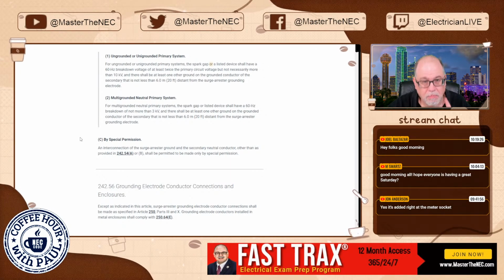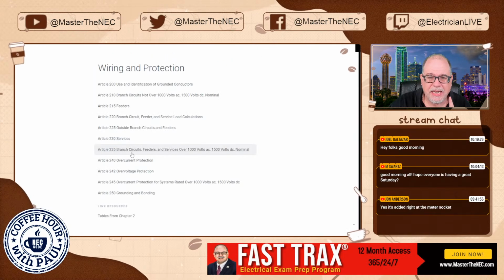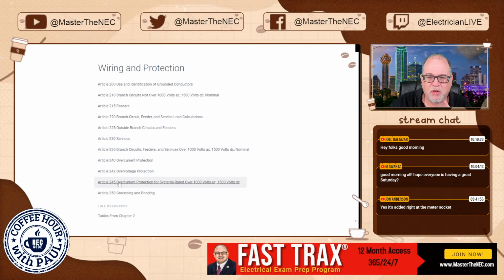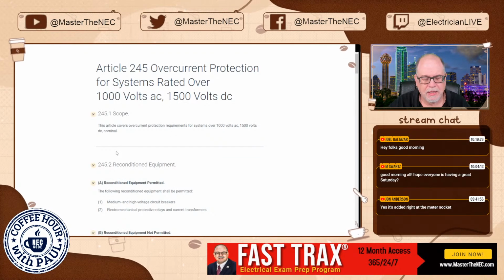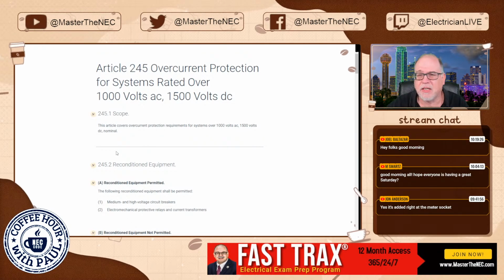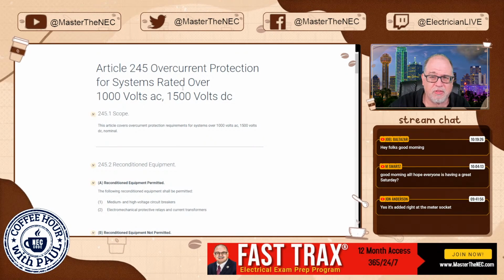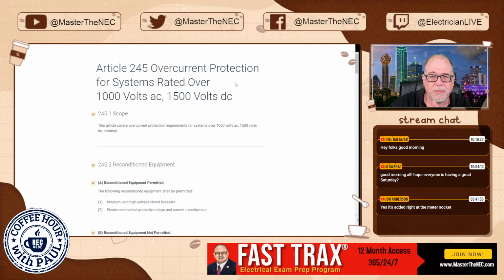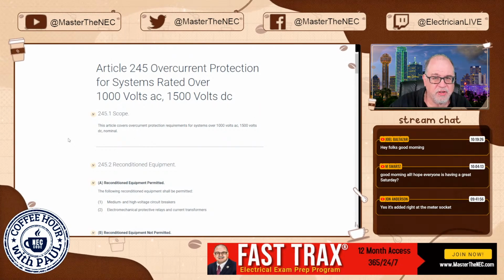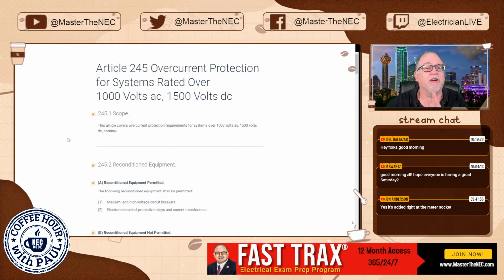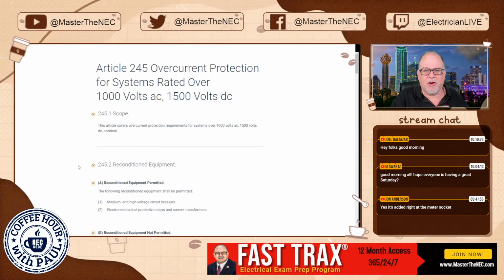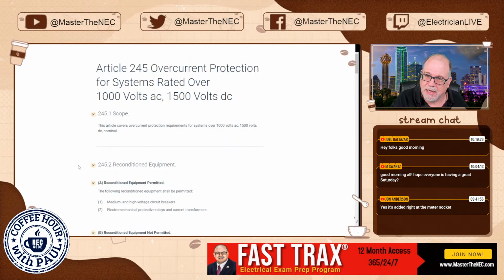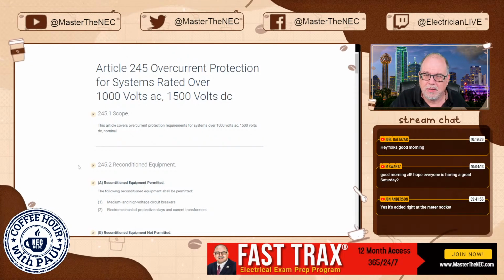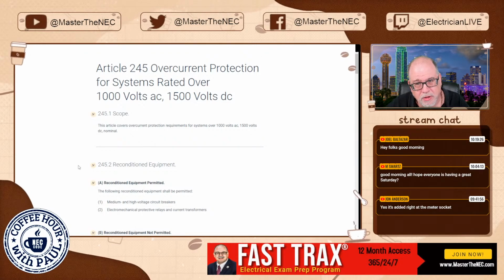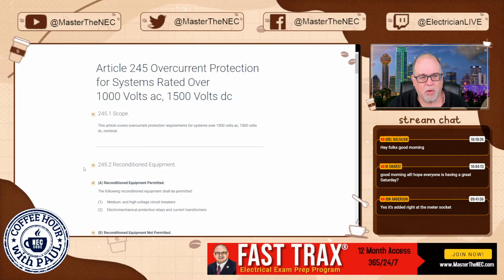All right. Now, one thing we're going to look at, and we're going to end this session, is what's called Article 245 now. So this is new for the 2023 edition of the National Electrical Code. And it makes sense. We have overcurrent protection for what? We have all of our overcurrent protection in 240 for 1,000 volts or less. We had to have rules for over 1,000 volt AC systems.